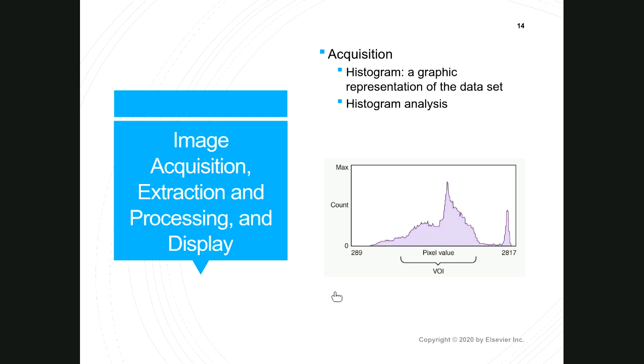That's why we constantly say that when you have those point processing functions of automatic rescaling in the lookup table, and I say that if you're over or underexposed, the image can appear with acceptable brightness and contrast, but it doesn't mean that you didn't over radiate or that there's not quantum noise exhibited. So the computer has a histogram that's based on a diagnostic image. And it takes the information that you're giving it and compares the two so that it can attempt to make it look like the diagnostic stored histogram as best it can.